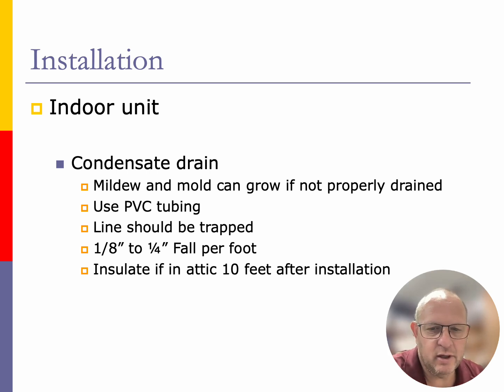Lines should be trapped like we discussed on the previous slide, with 1/8 to 1/4 inch fall per foot, and then insulate that at least 10 feet if you're in an attic situation or a situation where that condensate line will run into hotter air, and it would have the chance to condense moisture on the PVC pipe.